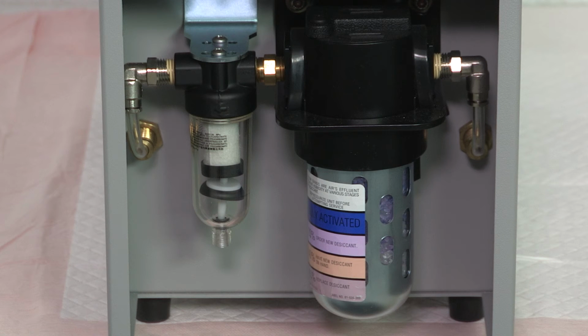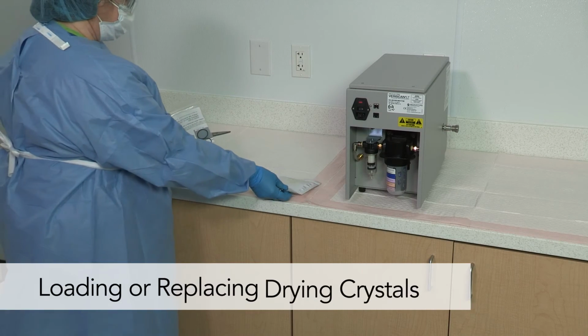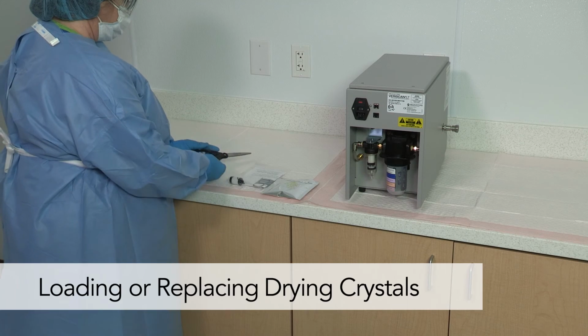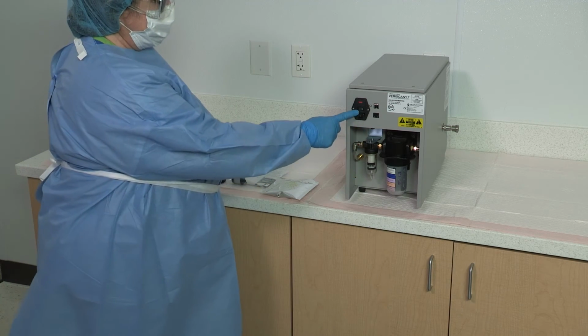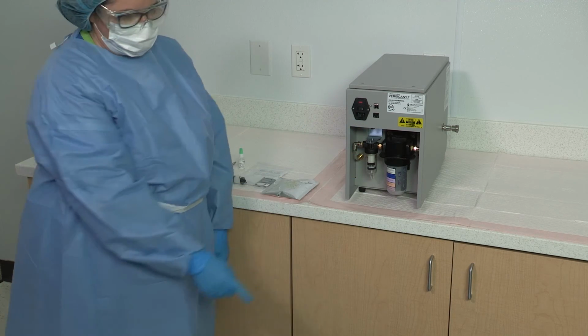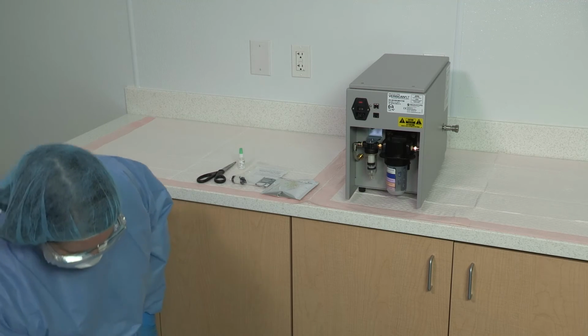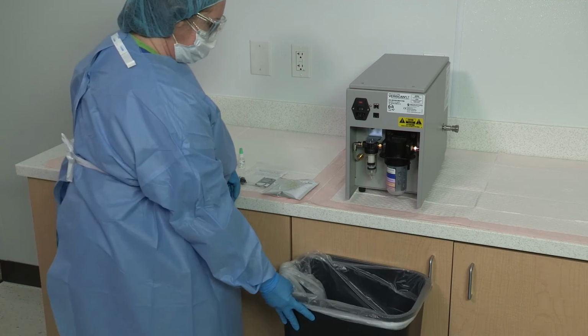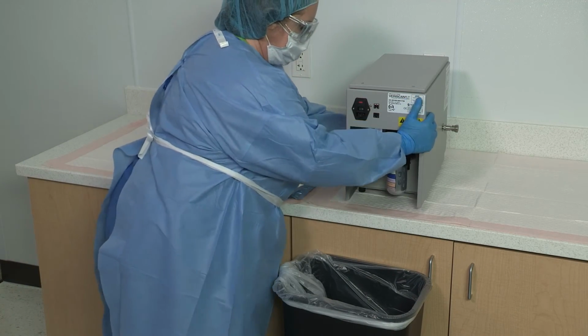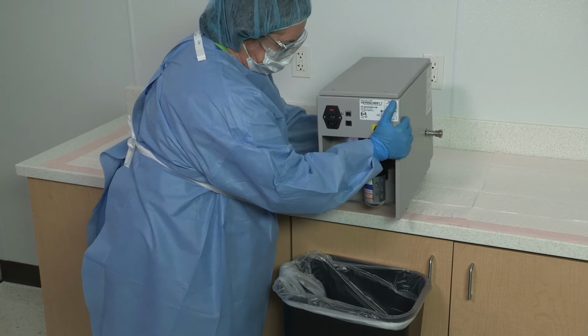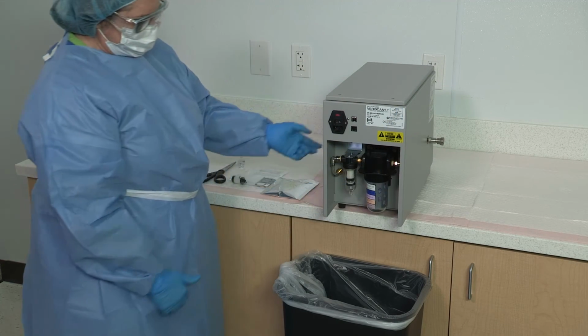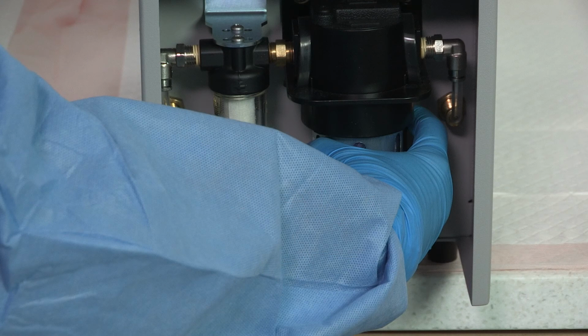Let's walk through the process of loading or replacing the drying crystals. First, locate a new unopened crystal desiccant bag. Turn off and unplug the VERISCAN Leak Tester before installing the drying crystals. Turn and carefully position the unit so the back is easily accessible. The recommended method for installing or changing the drying crystals is to extend 6 inches of the unit beyond the edge of the counter. Pull the metal housing release button down and hold.